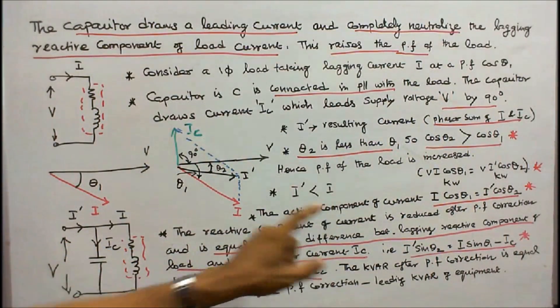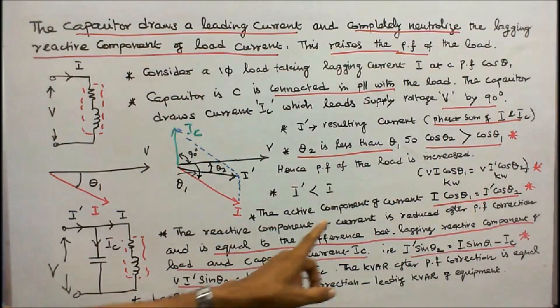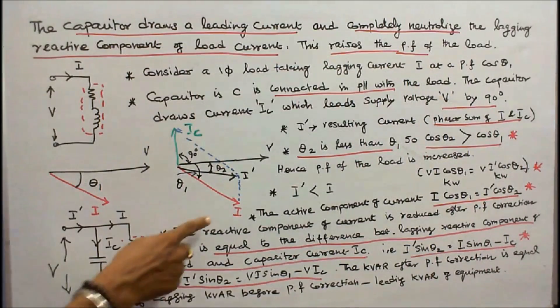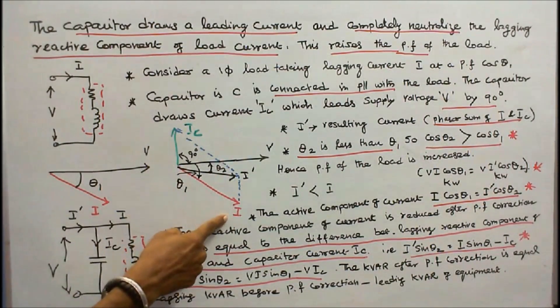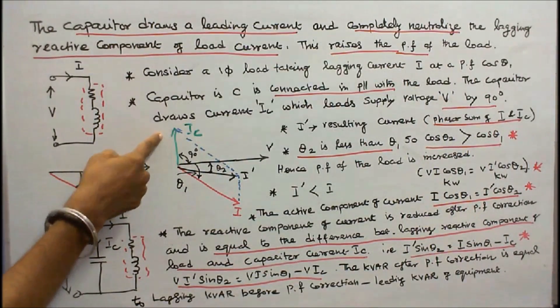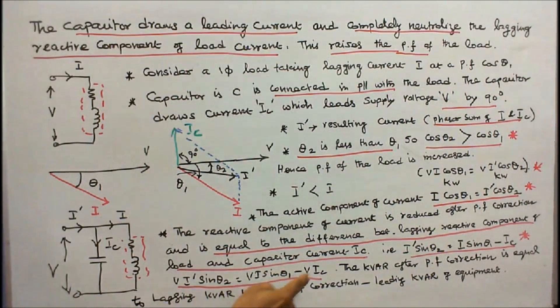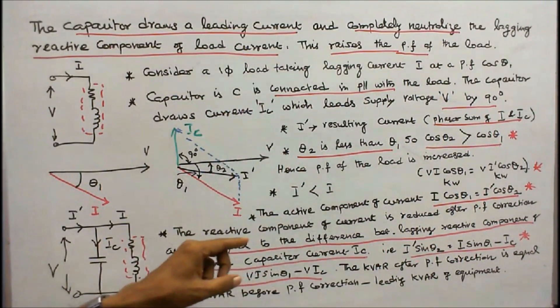The reactive component of current is reduced after power factor correction, and is equal to the difference between the lagging reactive component of the load and the capacitor current Ic. That is, I dash sin theta 2 equals I sin theta 1 minus Ic. Multiplying both sides by V: V I dash sin theta 2 equals V I sin theta 1 minus V Ic. Therefore, the KVAR after power factor correction equals the lagging KVAR before power factor correction minus the leading KVAR of the equipment.